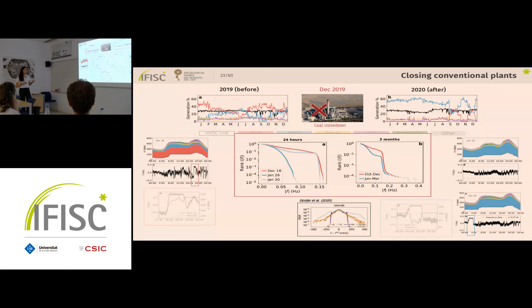And so we wanted to analyze these scenarios as well. So we use the same model as before that we used for Gran Canaria. However, now we have an extra equation to model the link dynamics. And this equation basically, under normal operation, so when the frequency stays within the 0.15 Hz limit, this control term is 0. So we simply force the power from the link to a reference power, and this reference power is given also by the data from the grid operator. And then when the frequency goes above or below plus or minus 0.15 Hz, this control term is activated, and this C-link here has a large value because the control acts very fast.